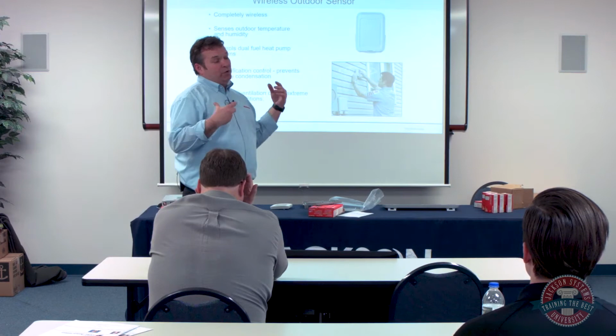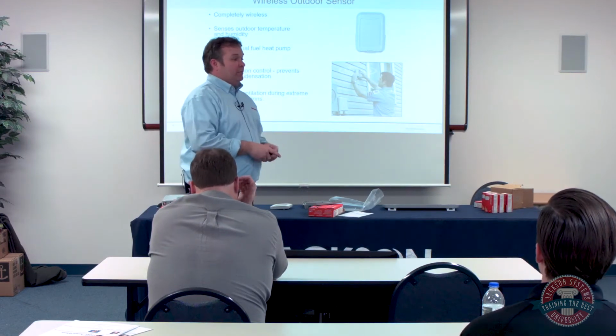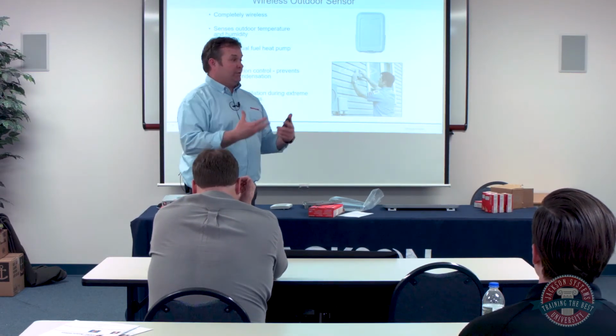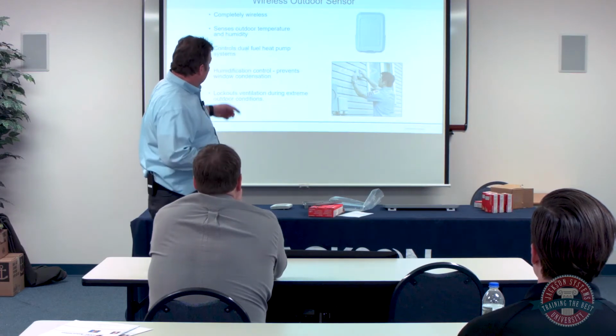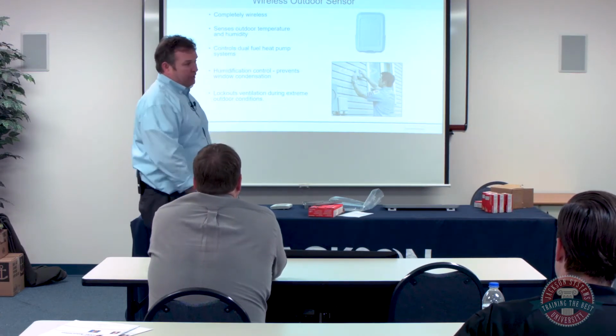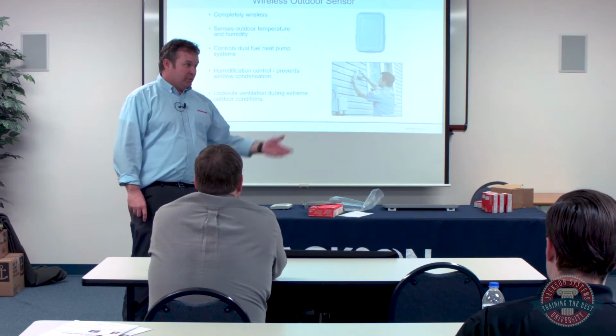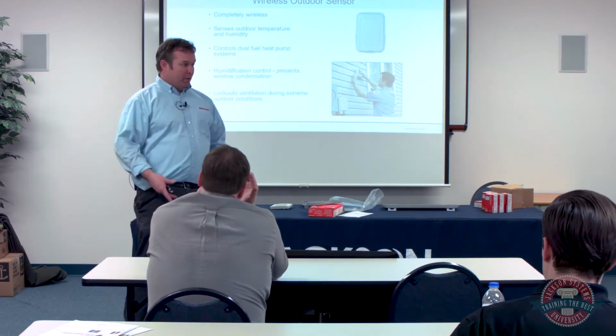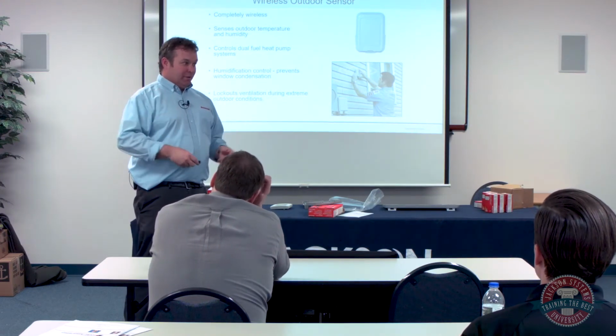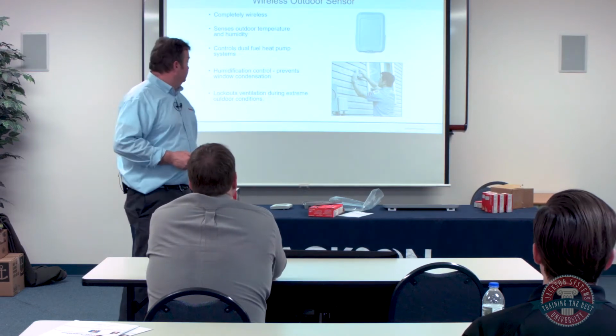Now if you use an ERV, that's not as much of a problem because you're recovering most of that heat. But it'll give you ventilation lockouts during extreme outdoor conditions, so instead of just opening up no matter the outside temperature, this does it a little bit better.